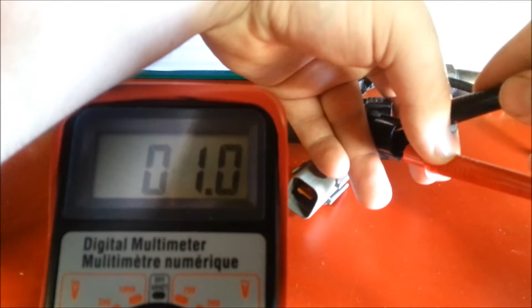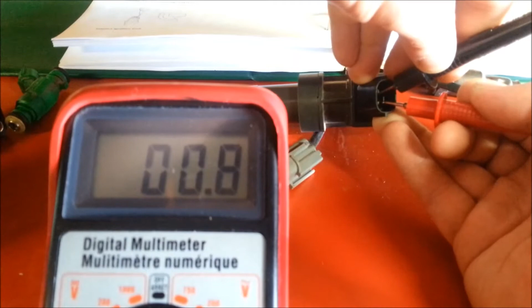This particular one is fluctuating all over the place. Once we get good, nice contact, it's saying 0.8, so we have more resistance than we should. We're looking for 0.62 plus or minus 10%, so the most we'd want to see is about 0.7 as an acceptable value.